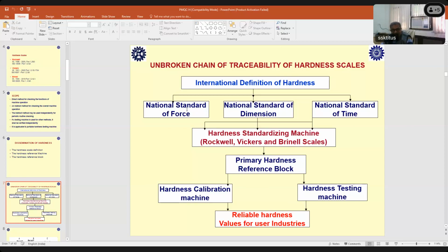I have already mentioned how much force you are applying on a sample, and the national standard of dimension, because after making the indentation you are going to measure either the depth or the diagonal or the diameter, depending upon the scale. That is, the deformation made on the sample by the indenter, particularly the area of the indentation. So a dimensional component comes into the hardness measurement. We need to make sure the dimensional component you are measuring on the deformation should be traceable to the national standard of dimension, and the national standard of time.